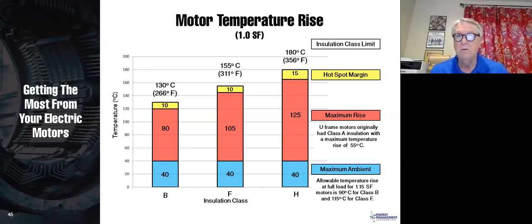So let's start with our motor temperature rise. This is a review from last time. Typically motors come in B, F, and H insulation. Now if you've got an old U-frame motor, that U-frame motor may have had a temperature rise of 55 degrees C. And so a lot of people think, boy, those U-frame motors, they were really good because they run so cool. Well, yeah, they do, but they are also very large and pretty expensive.